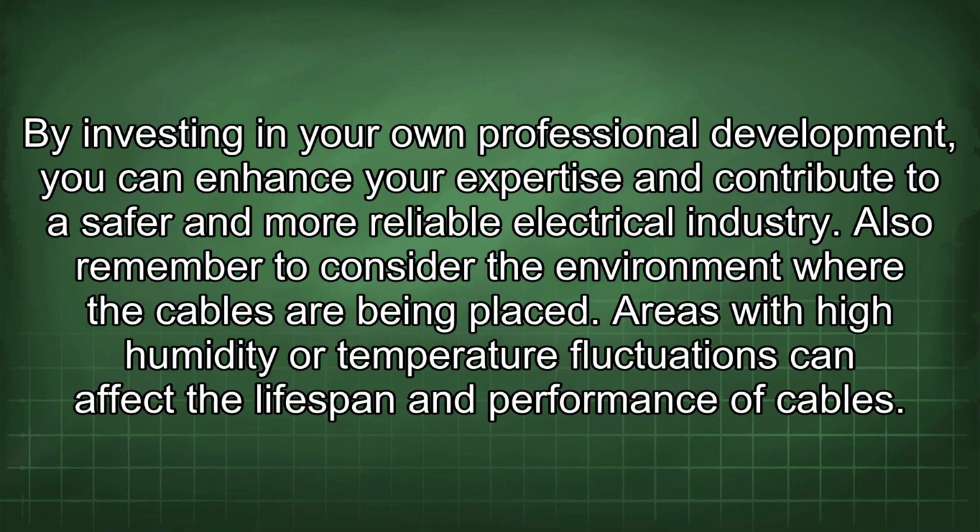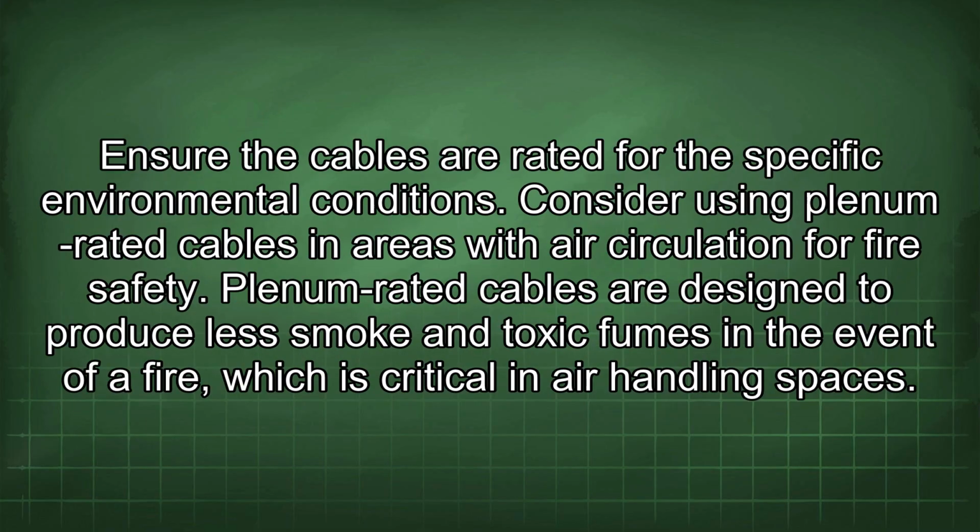Also remember to consider the environment where the cables are being placed. Areas with high humidity or temperature fluctuations can affect the lifespan and performance of cables. Ensure the cables are rated for the specific environmental conditions. Consider using plenum-rated cables in areas with air circulation for fire safety. Plenum-rated cables are designed to produce less smoke and toxic fumes in the event of a fire, which is critical in air handling spaces.